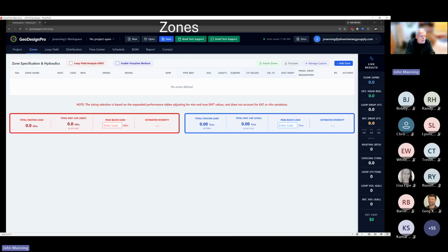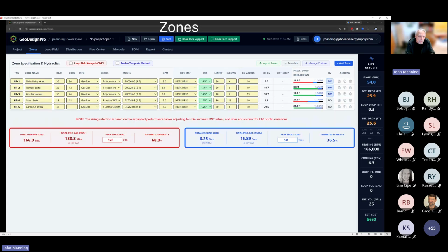So the next tab is zones, and you can identify each zone that is being served by a particular heat pump. The process is quite fast. Oh, maybe not that fast, but step by step you add your zones. You can override the default tag nomenclature. You can override the zone name, customize it any way you want. You input heating and cooling loads in kBtus per hour. The default manufacturer pops up, but you can override that.